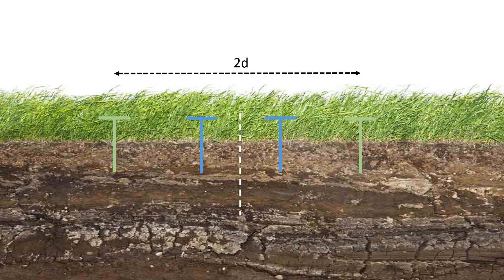This method saves considerable time in the field, particularly when you want to carry out several soil resistivity measurements for a profile of the terrain. The extra time saved is due to the fact that only the two outer electrodes need to be moved to obtain a new measurement at a different depth.